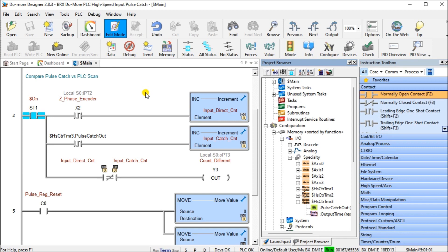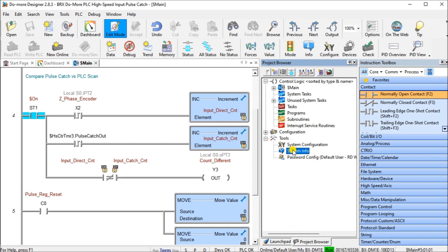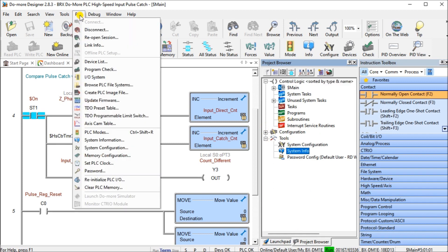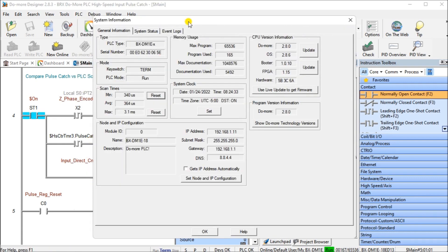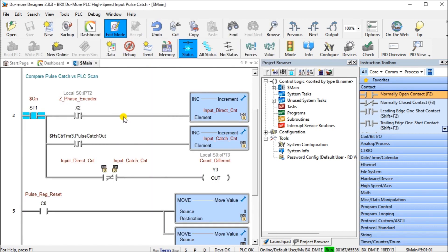Next, if we take a look at the actual scan time of the PLC, which is available within the BRX Do-More PLC, we can hit the info button, or we can take a look at the system info, or we can go PLC and then system information. What you'll notice is that we have our minimum, our average, and our maximum scan time of our PLC currently, and we can reset those if we wish. That pulse has to be at least 200 or 300 microseconds in order for the PLC scan time to see it. But because the high-speed inputs operate asynchronously with the PLC, it'll pick up a lot quicker.